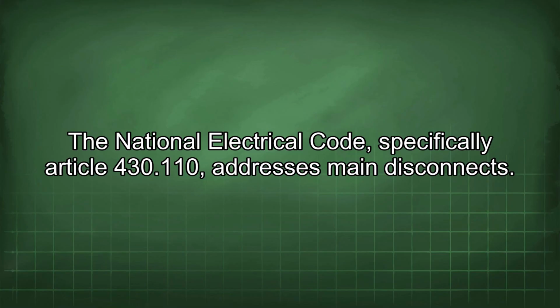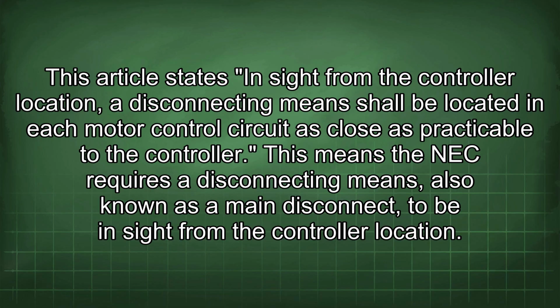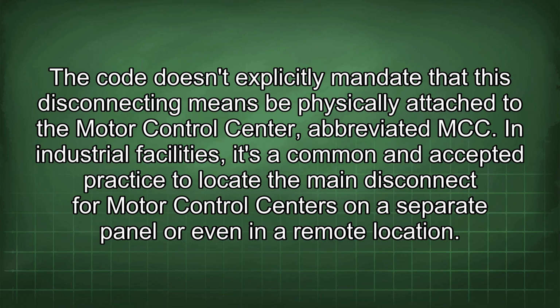The National Electrical Code, specifically Article 430.110, addresses main disconnects. This article states that in sight from the controller location, a disconnecting means shall be located in each motor control circuit as close as practicable to the controller. This means the NEC requires a disconnecting means, also known as a main disconnect, to be in sight from the controller location. The code doesn't explicitly mandate that this disconnecting means be physically attached to the motor control center, abbreviated MCC.